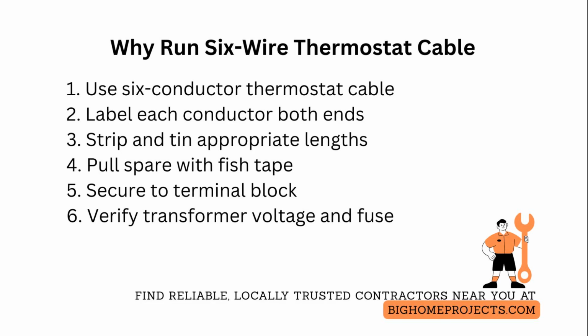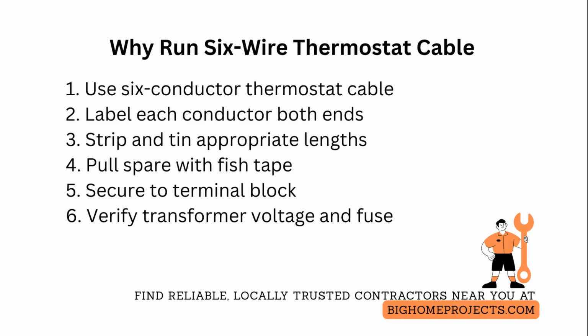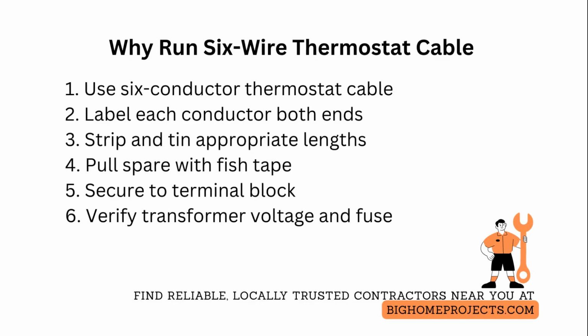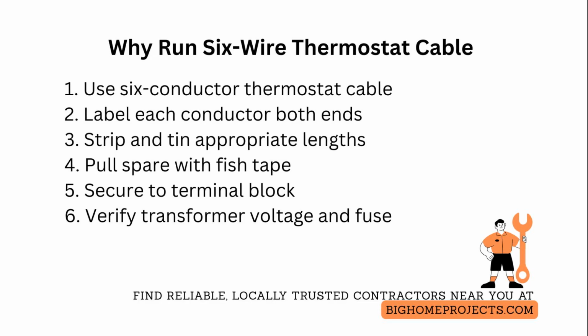Verify voltage and transformer compatibility with a multimeter and document the transformer secondary voltage and fuse rating on your installation sticker. Smart thermostats often need a dedicated common wire for charging, and intermittent charging symptoms are almost always a loose common or incorrect transformer.